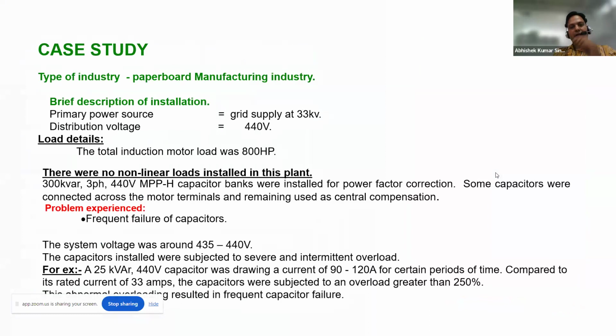So this is regarding a paperboard manufacturing industry. There was a load of motors, and the entire plant did not have any non-linear load. All the loads were linear. But what was happening? Their capacitors were getting damaged again and again, so they were quite tense.